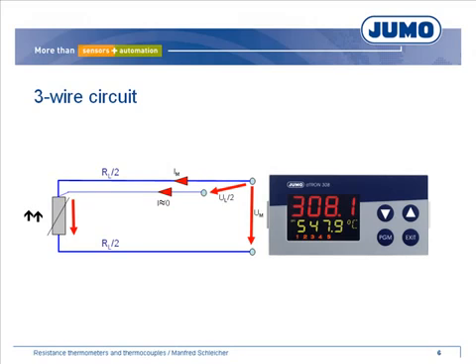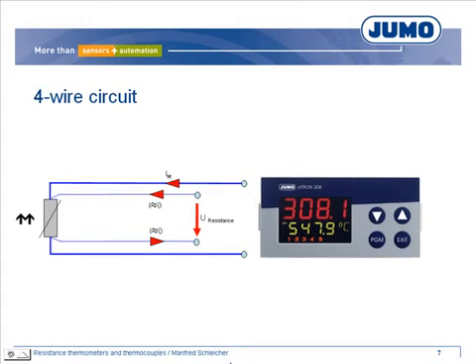A precondition for an accurate result is that both wires have the same resistance value. Using a four-wire circuit, the voltage drop is measured directly on the resistance thermometer. The resistance value can be calculated using the voltage drop on the resistance thermometer and the measuring current. The resistance values of the leads and contact points can differ, and the four-wire circuit has the lowest measuring inaccuracy.